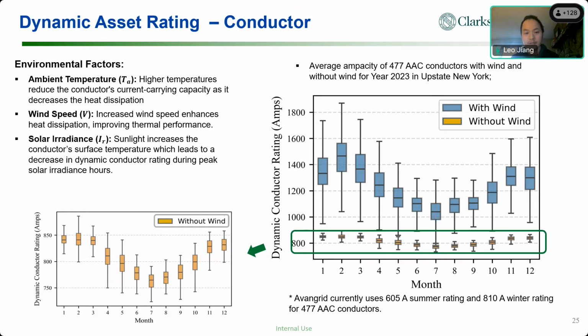Now, if you look at the figures on the right, with and without wind speed, what is the maximum current the same conductor can bear? If you zoom in on the yellow, that gives you the figures at the bottom left. You can see that even in the hottest summer time, the bearing current of the conductor can go beyond 605 amps. That means if you are in a flexible interconnection, where the main lines or feeder circuit could be the limiting element, then with dynamic asset rating for the conductor, you can get additional capacity. Next slide, please.